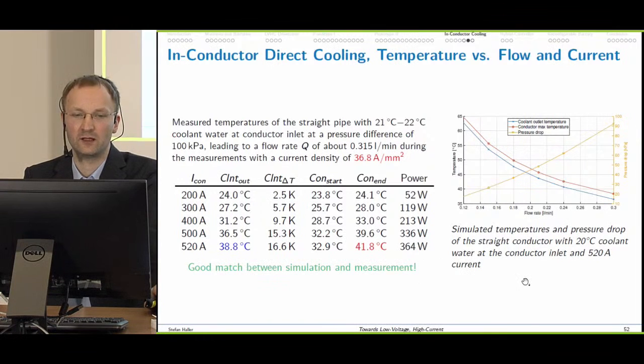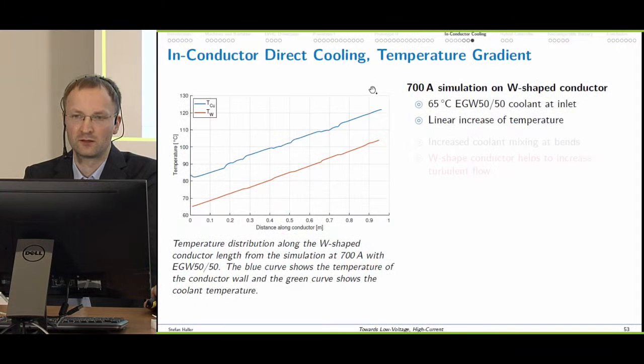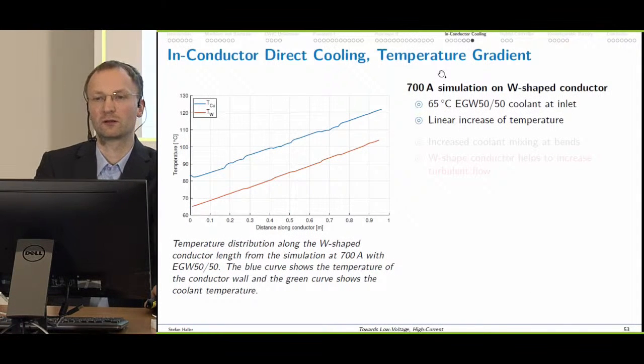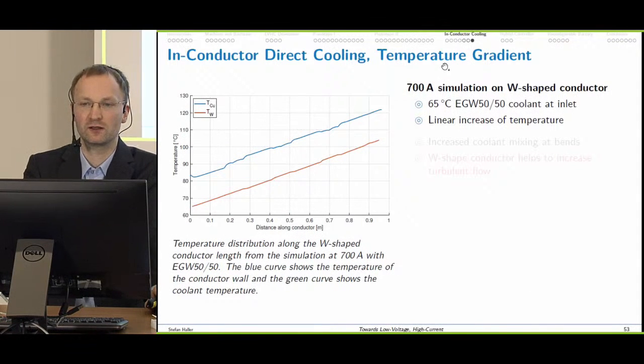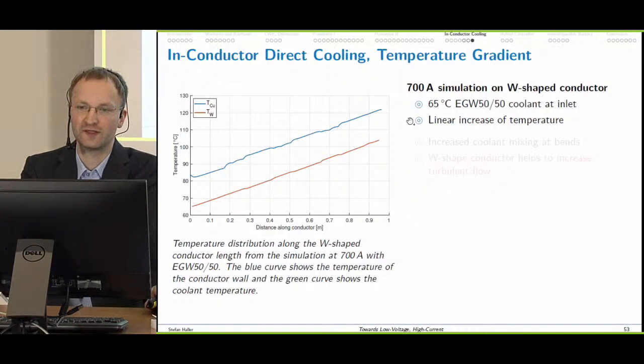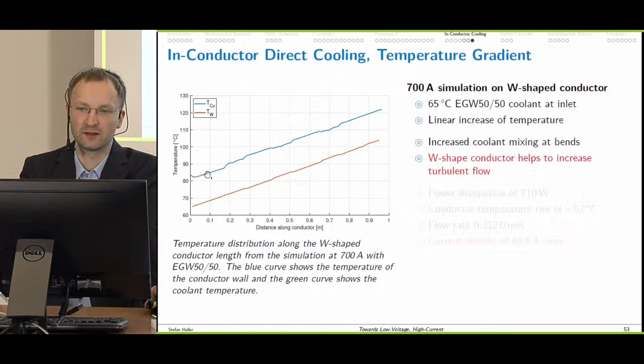All in all, we can say we have a good match between simulation and measurements here. The last one I like to show here for the conductor cooling is the temperature gradient. This is the 700 ampere simulation of the W-shaped conductor. We used 65 degree hot coolant, which is here, and we see a linear increase of the temperature. We can also see that we have an increased coolant mixing due to the bends here. And the result is that the W-shaped conductor helps us to increase turbulent flow.